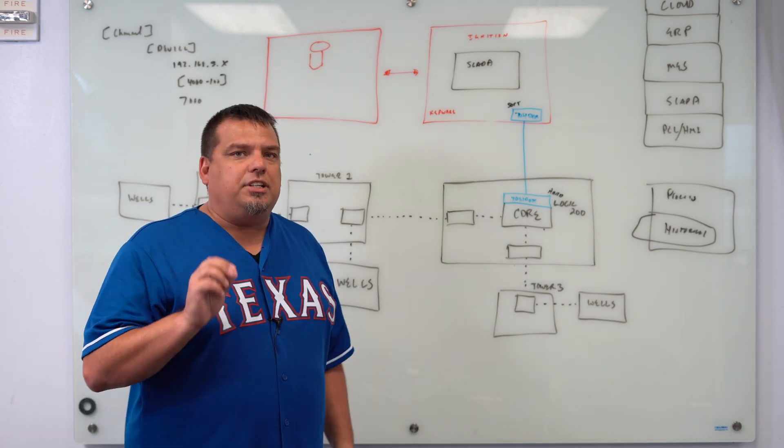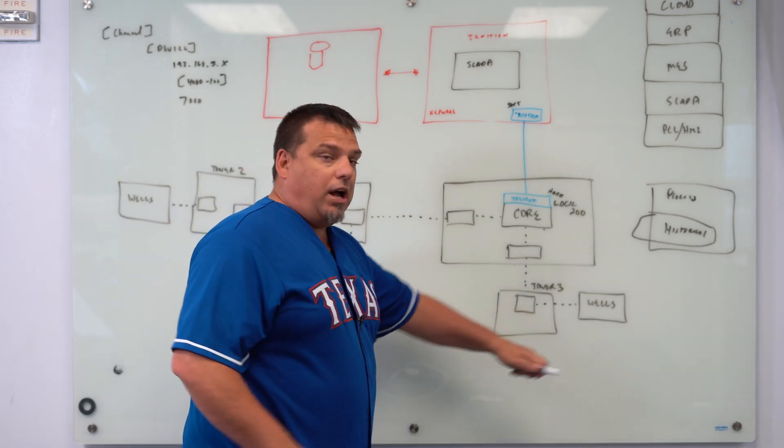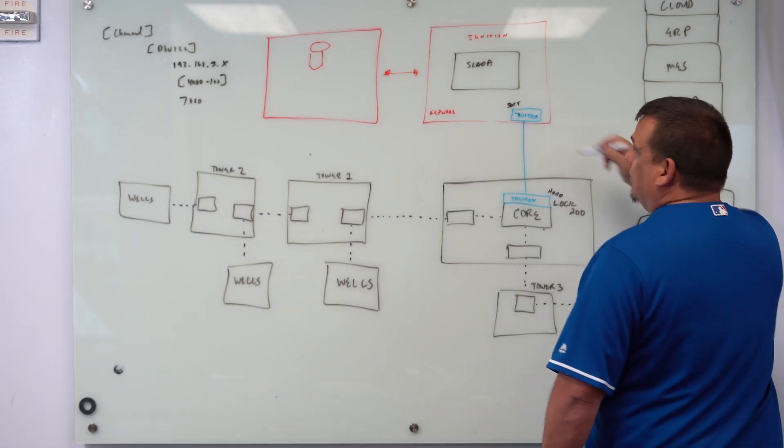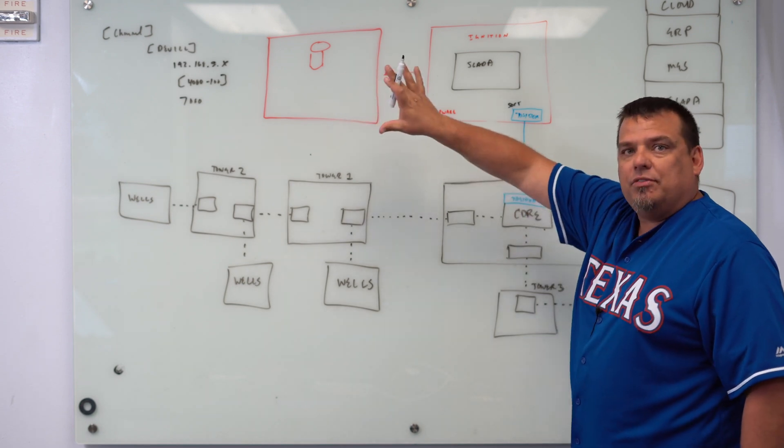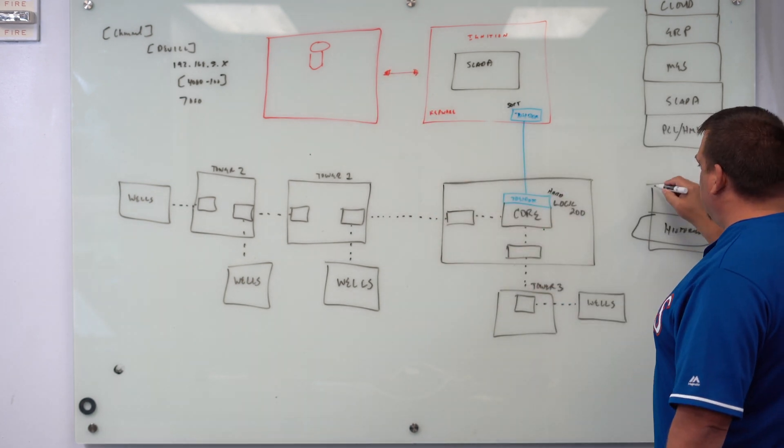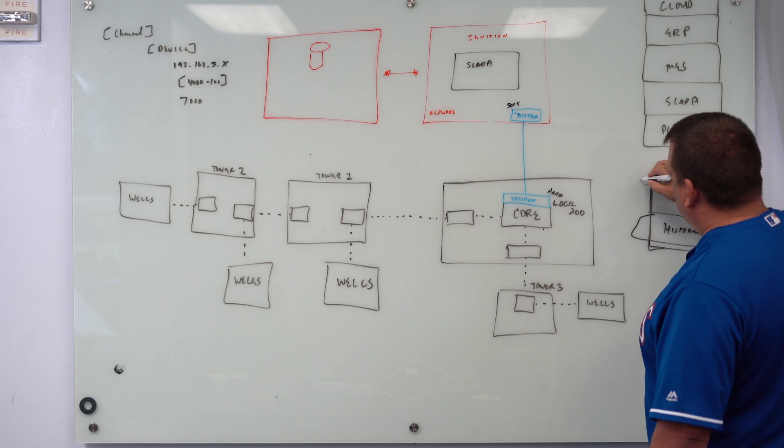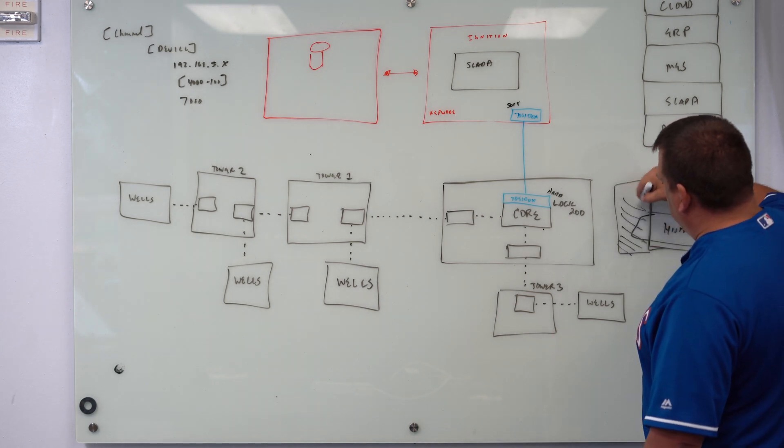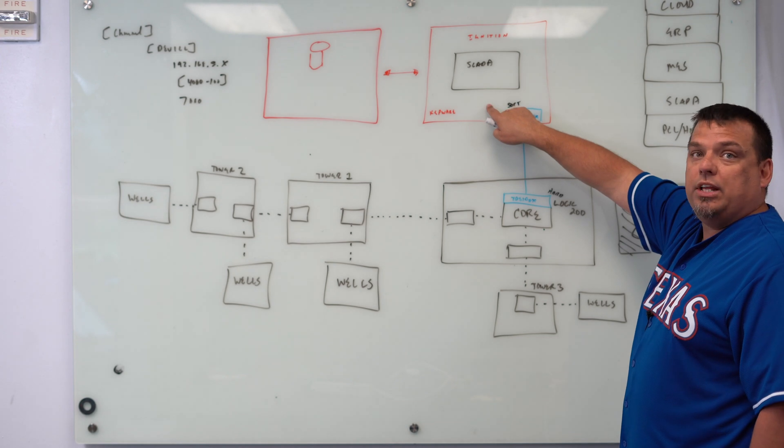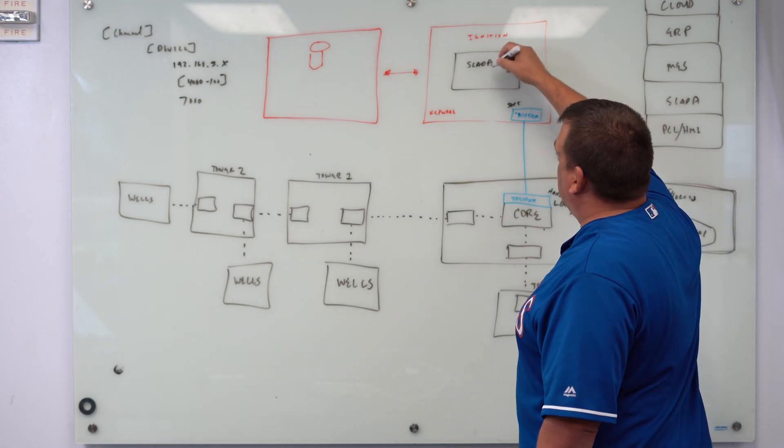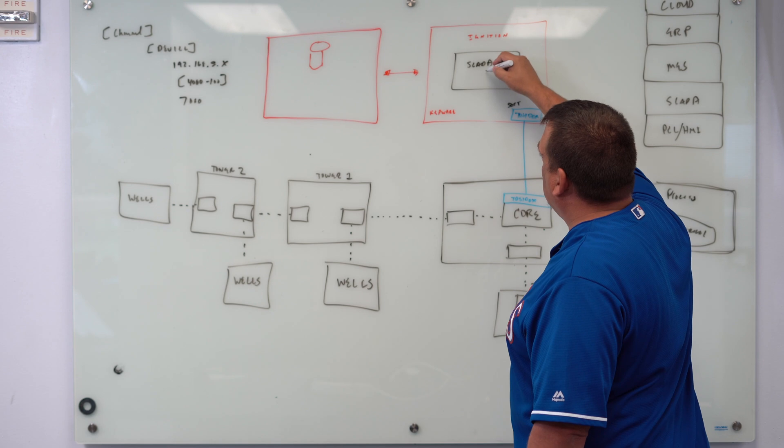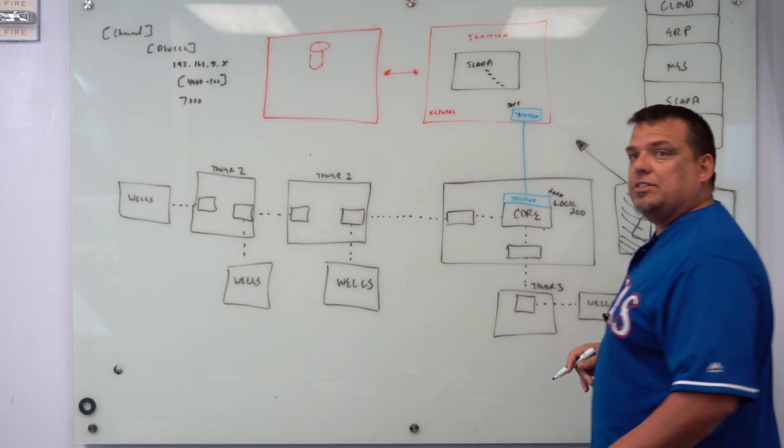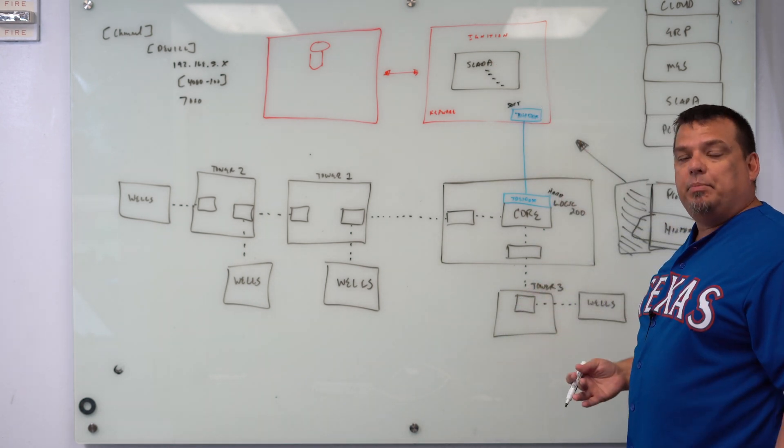In an IIoT infrastructure, when I've got my well out here on the edge with my ABB total flow, instead of having to engineer all of those connections, what we're going to do is take the ABB total flow and put an edge device on it. This is the IIoT edge device, and then we're going to point it to our SCADA system. Inside Ignition acting as our MQTT broker, all of our tags, all of our connections to the wells are just going to appear.